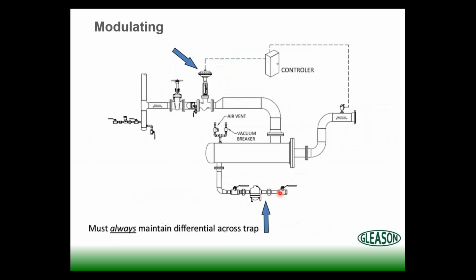On the other side of that, we've got modulating applications where we actually are controlling the steam coming into the heat exchanger. In this case, we've got a control valve, right? Steam's coming in, we're feeding our steam into our unit, and this valve can close down to 0. Bottom line, something we always need to remember is we must always maintain a differential across the trap. So if it is a modulating application where this can close down to 0, we must gravity drain across the trap. Now, if we want to gravity drain into a tank or a pump and then pump it up to an overhead return, we can certainly do that. But we need to make sure we're all on the same page with the terminology: modulating versus non-modulating applications.